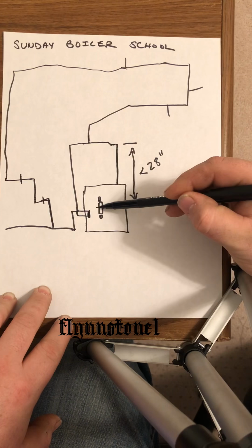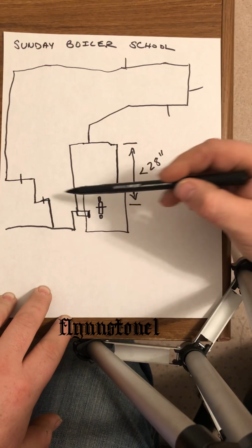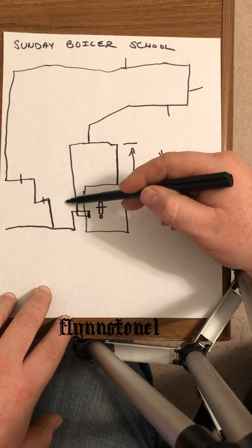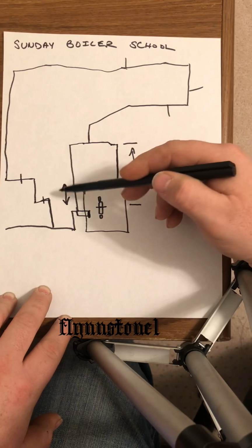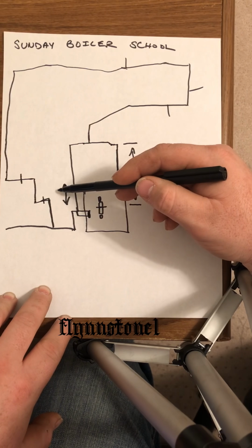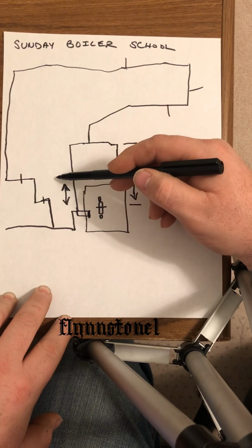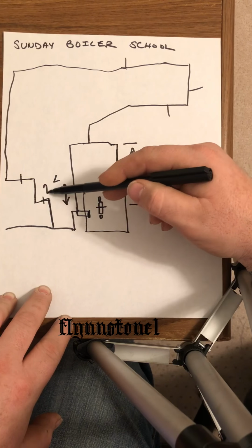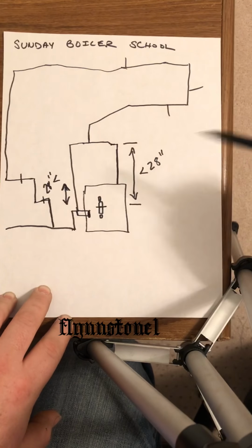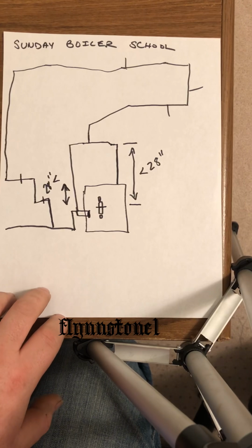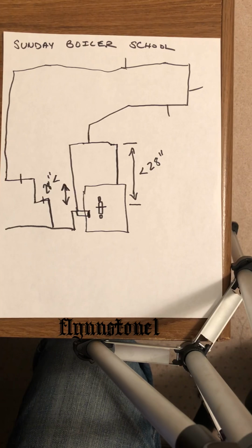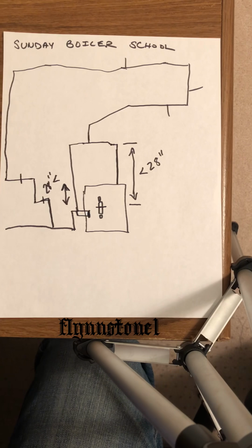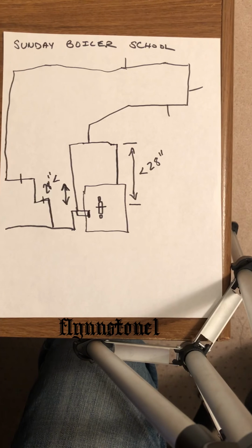Because in the horizontal it is still steam carrying, you lose your A dimension here. So now this is less than 28 inches, and it can cause some serious water hammer because the pressure from the boiler is pushing the water away and out of the boiler.